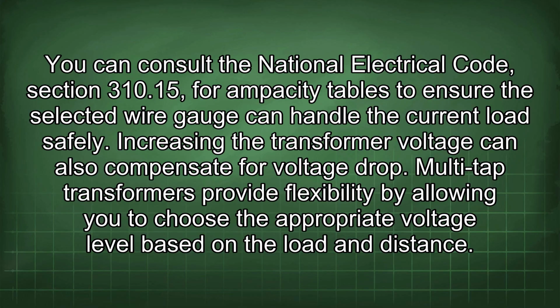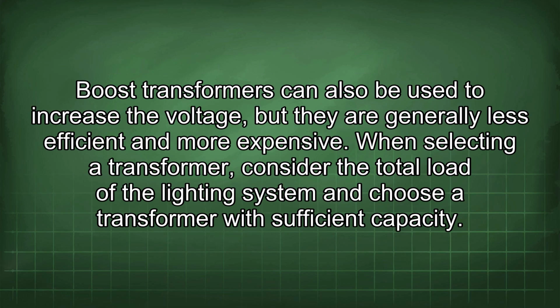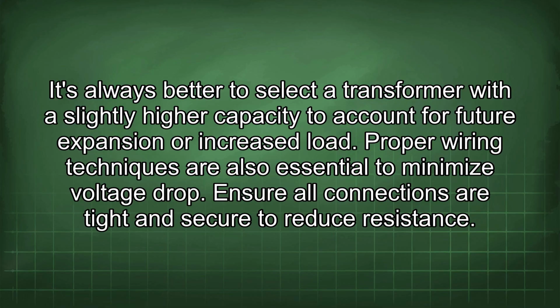Multi-tap transformers provide flexibility by allowing you to choose the appropriate voltage level based on the load and distance. Boost transformers can also be used to increase the voltage, but they are generally less efficient and more expensive. When selecting a transformer, consider the total load of the lighting system and choose a transformer with sufficient capacity. It's always better to select a transformer with a slightly higher capacity to account for future expansion or increased load.